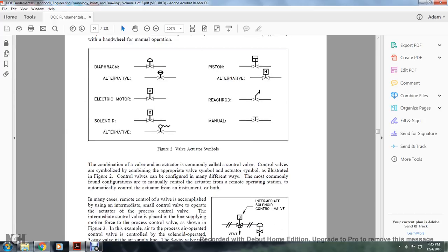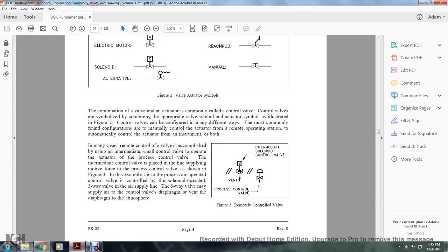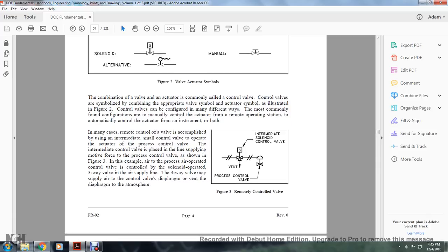The combination of a valve and actuator is commonly called a control valve. Control valves are symbolized by combining the appropriate valve and actuator symbols. The most commonly found configurations are: manually controlled with an actuator remote operation station, automatic control from an instrument, or both. In many cases, a remote control valve is established using an intermediate small control valve to operate the actuator of the process control valve. The intermediate control valve is placed in the line supplying motive force to the process control valve, as shown in Figure 3.